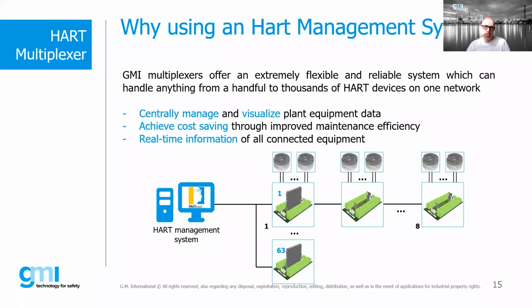It supports the management of different standards from different manufacturers, also mixed, and through the board interface, the signals are collected and transmitted to a PC to be supervised. Thousands of signals can be managed in a single network, allowing real-time communication of all connected equipment. While the sensor constantly transmits its analog measurement, the control unit can read and modify the local sensor settings, for example, the measuring range, via HART overlapping the 4-20 milliamp signal and without interfering with it.